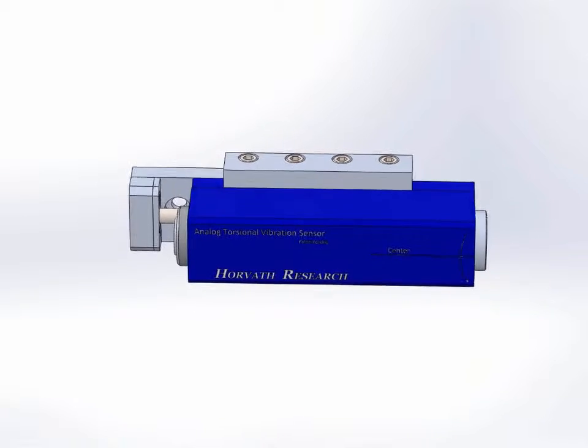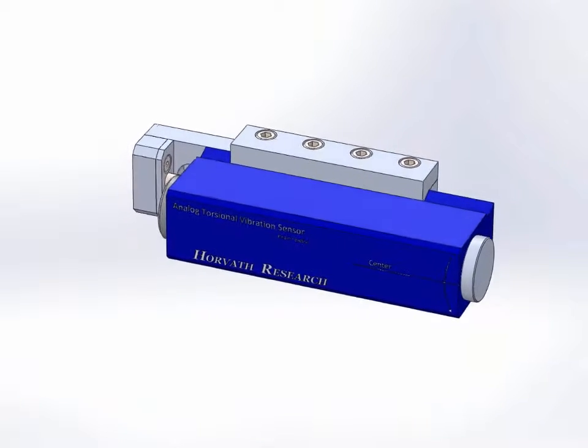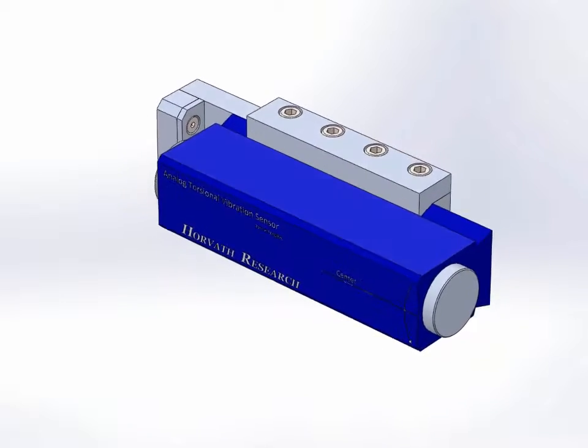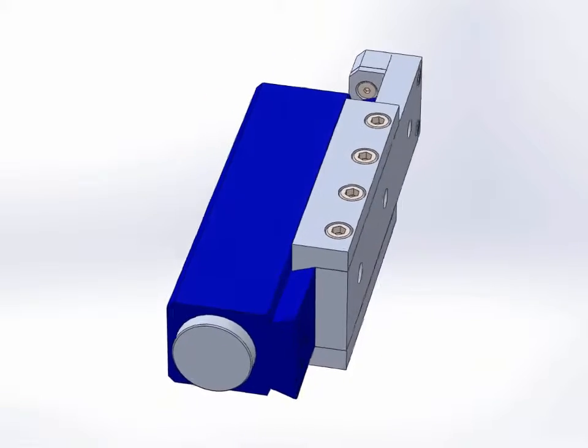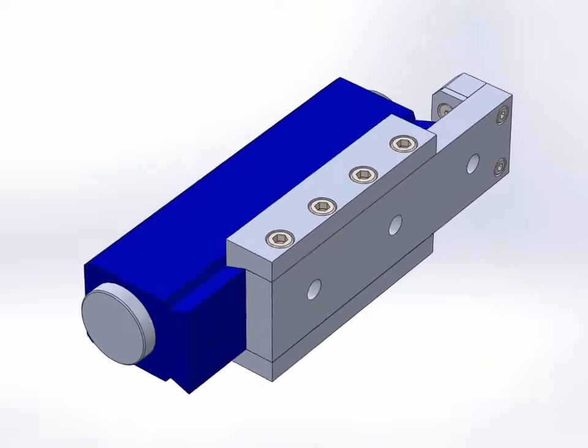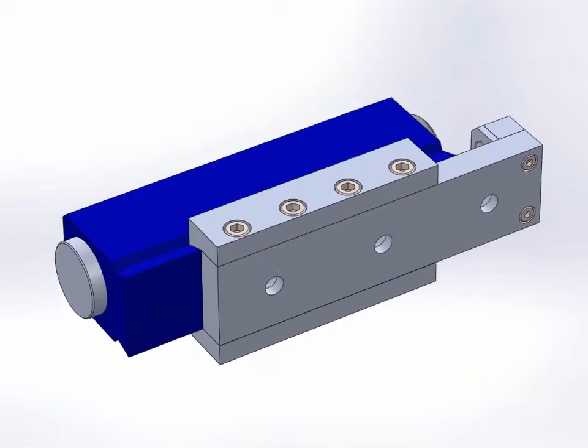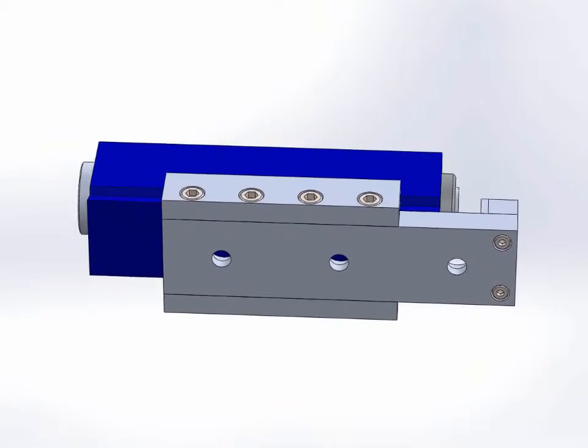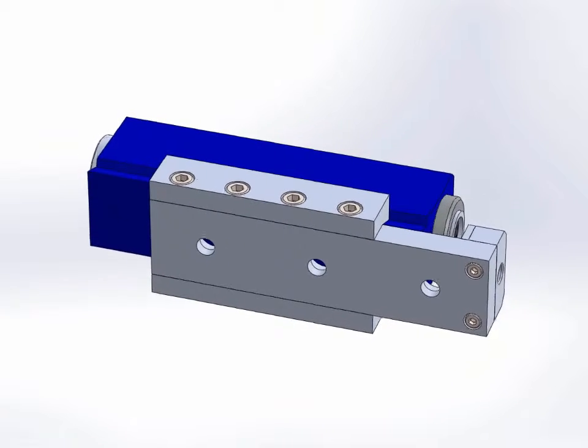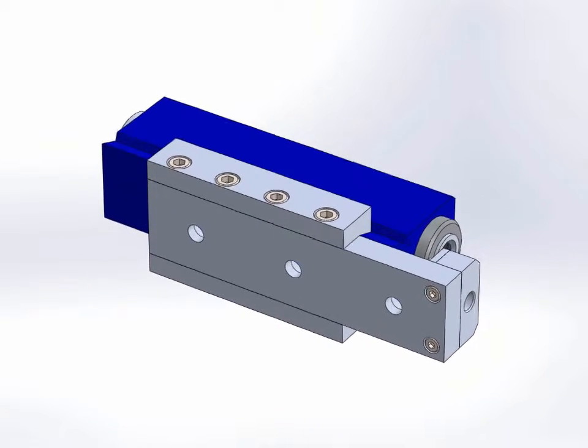The analog torsional vibration sensor was developed to address the industry's need for an analog sensor that provides reliable data to identify torsional vibration without the installation of encoders, slip rings, and telemetry. ATV-S is a contactless sensor. Similarly to radial vibration probes such as proximity probes, a small section of exposed shaft surface can provide sufficient target area to measure torsional vibration.